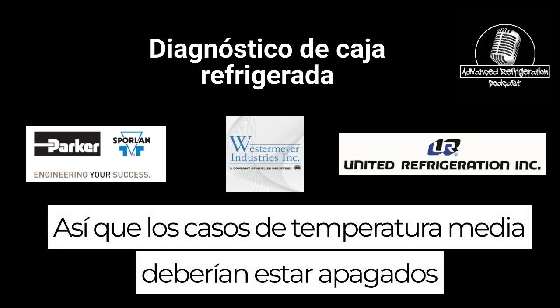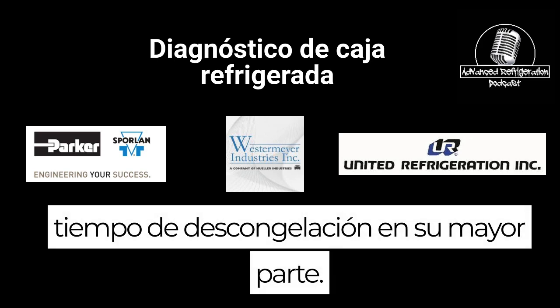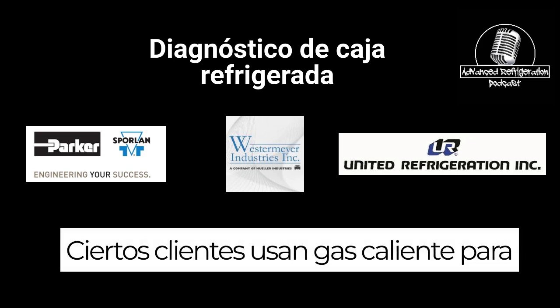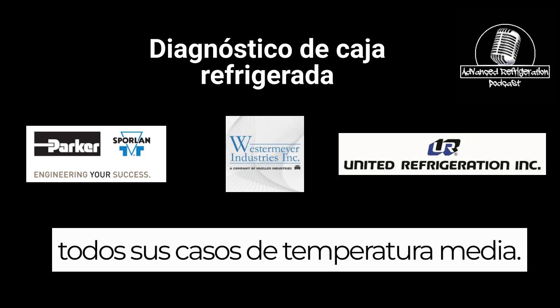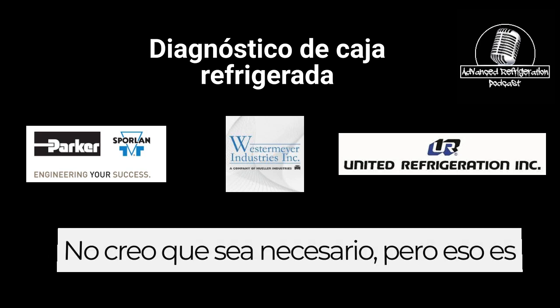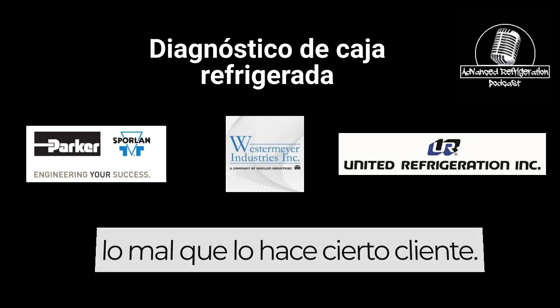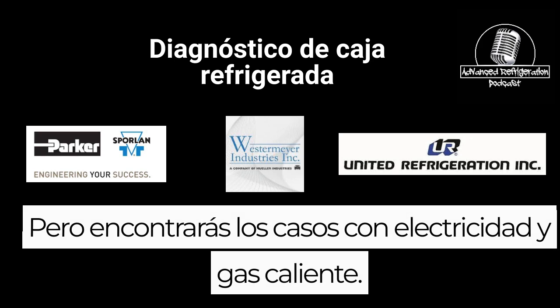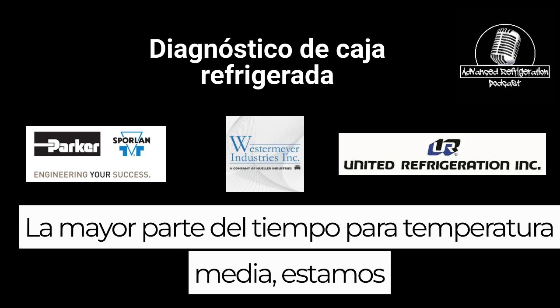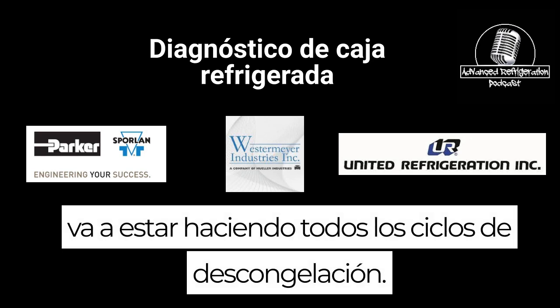So medium temp cases should be off-time defrost for the most part. Certain customers use hot gas for all their medium temp cases. I don't think that's necessary, but that's just how that certain customer does it. But you will find some cases with electric and hot gas. Most of the time for medium temp, we're going to be doing off-cycle defrost.